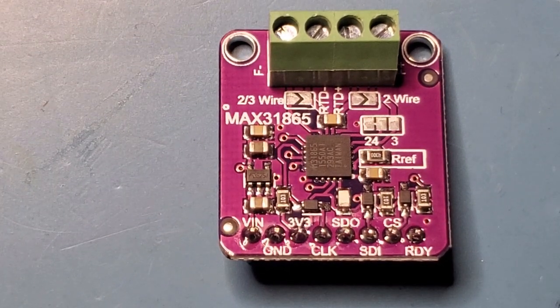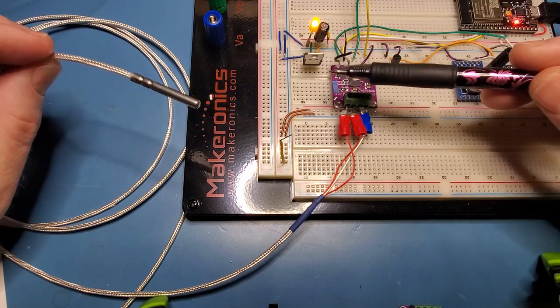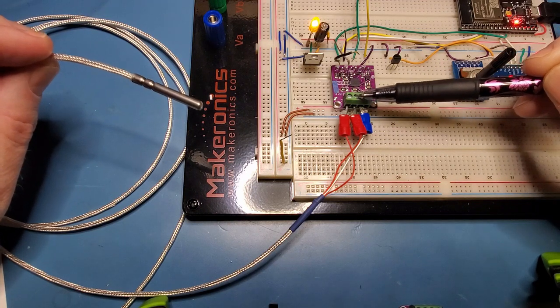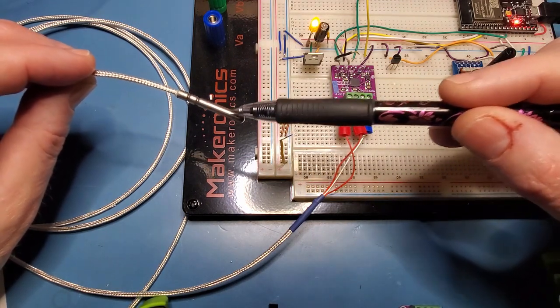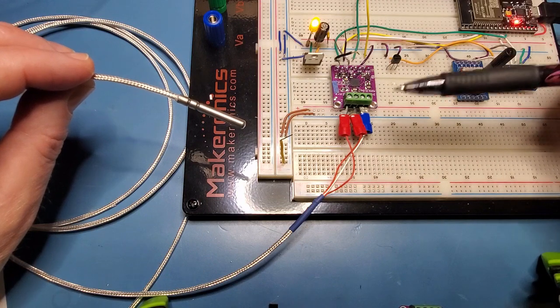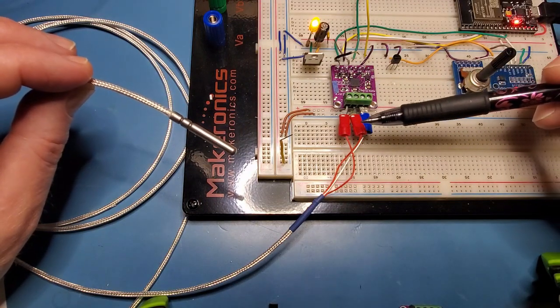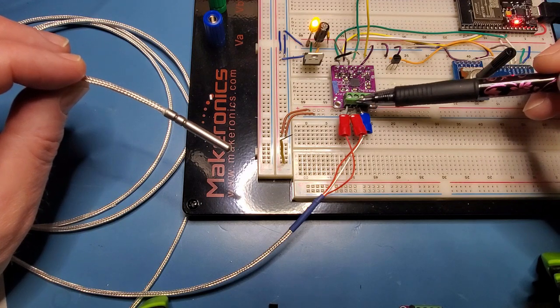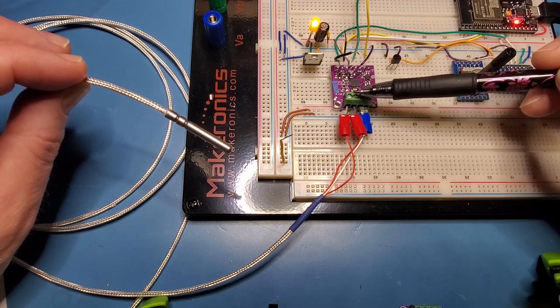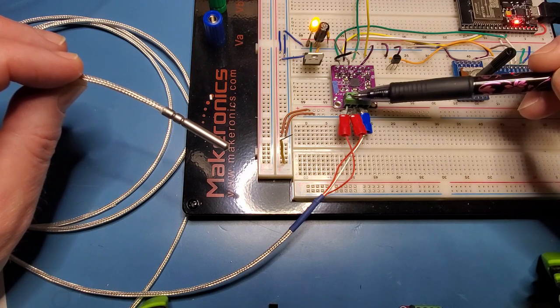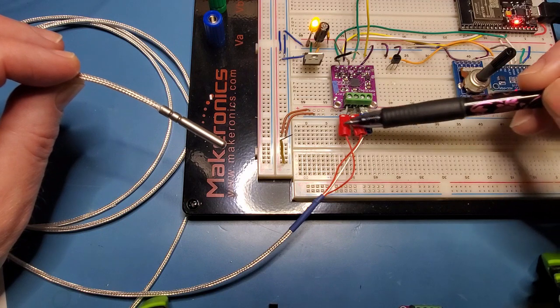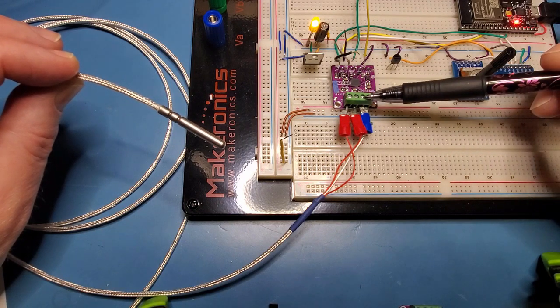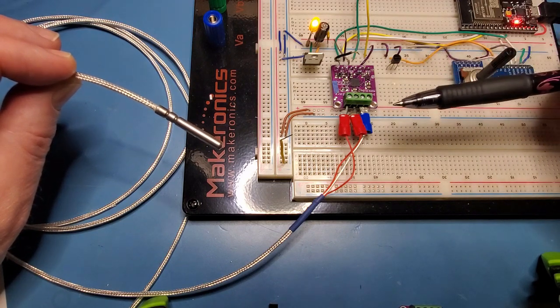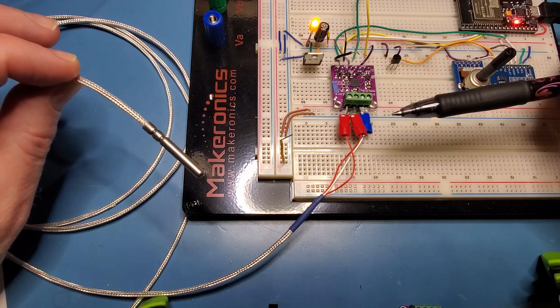Let's move on and look at the probe now. Here's the probe, the 3-wire probe, connected to the MAX board - note the board is actually upside down from the orientation I had before. There's a piece of platinum wire inside which responds to temperature by changing resistance. For the 3-wire probe connections: the two leftmost connections go with the common, the two red wires, and this connection is for the blue wire. This pin and this pin are shorted together depending on the bridge selections you've made.